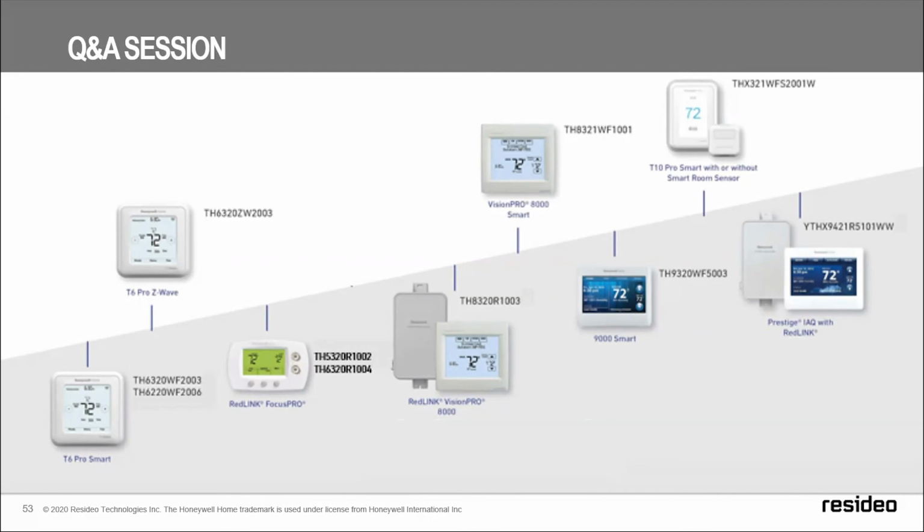It's purely an accessory. So the ERM can be used for, I'll give you a couple of examples, changing out from an AC unit to a heat pump. You can use the ERM there to take the two wires, R and C, convert them there, and then communicate back wirelessly to either an 8000 or the EIM. And that would be a labor savings, because you don't need to run those wire sets, particularly where that's not always easily done. This allows you to do it very unobtrusively.